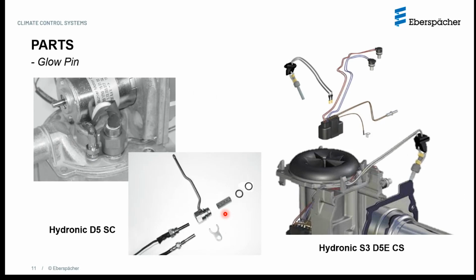That is the glow pin. It's a very important part. Both the first generation and the third generation have glow pins because obviously they have to ignite the fuel. These glow pins will be preheated for at least approximately 40 seconds before the fuel supply is activated. This allows the glow pin to be at the right temperature so that when the fuel arrives, it can be ignited quickly. Over here on the first generation, you can see the location of the glow pin. The glow pin is fitted into this fitting, and you can see another picture below it that shows the fuel fitting. So your fuel is supplied through these lines into the fitting, and your glow pin is seated inside that fitting. Also inside that fitting is what we call a glow pin screen.